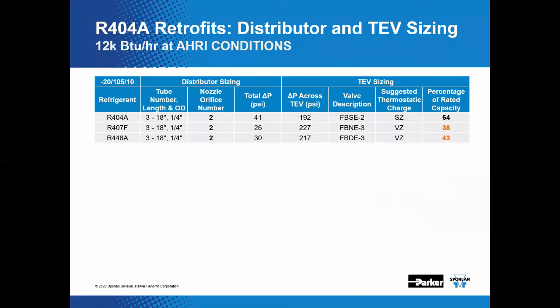We are considering a retrofit on an R404A system here, and we're looking at a 1-ton load on a low temp system. Using the Sporlan selection program, we select an R404A distributor and a TEV. We select a number 2 nozzle assembly like you see here, giving us 41 psi total delta P, distributor and tubes. Using that number and assuming a 5 psi drop through the high side lines, we have 192 psi drop across the TEV. That's the number you see here.